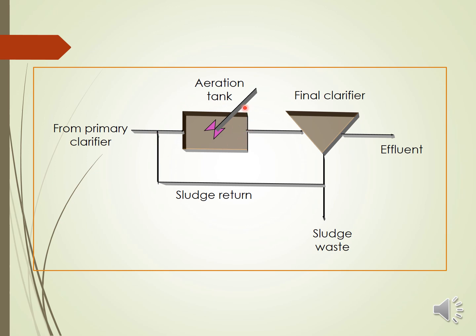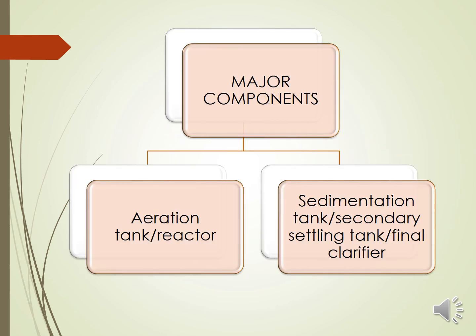In the aeration tank, the wastewater is aerated to provide oxygen for the microorganisms to grow and decompose the organic matter. In the final clarifier, the biomass or bacteria is separated from the wastewater. The clear water is discharged as effluent, and the active sludge — which contains a very active concentration of microorganisms — is returned back to the aeration tank. The two major components are the aeration tank and the sedimentation or secondary settling tank.